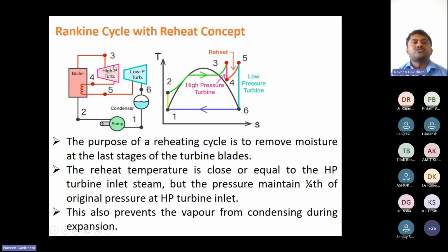Why is it so? Suppose the output of the HP turbine is used in the IP turbine; there is already a loss of heat and temperature. Generally, this condition is 35 kg and 333 degrees centigrade, as per our practical experience. If we supply this steam to the IP turbine, there is a chance of condensation. There is an enormous release of condensation, and moreover the fumes, which is going to damage the turbine blades. There is enormous drainage, and moisture content is there.